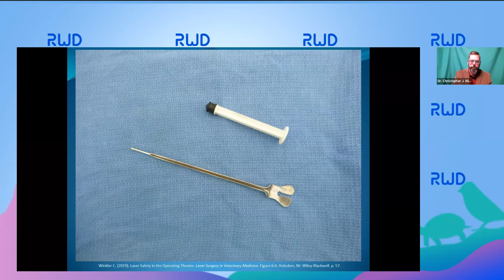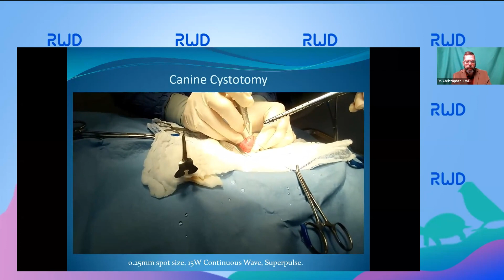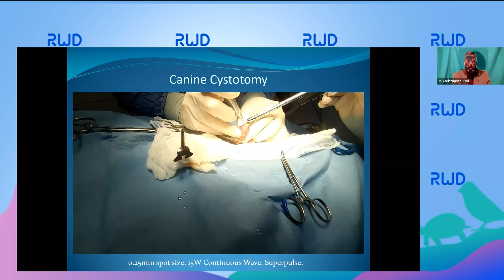Cystotomy is a very satisfying procedure with a CO2 laser. This laser here is set for a 0.25 millimeter spot size at 15 watts continuous wave superpulse. It offers great hemostatic control. Postoperative hematuria and discomfort have been non-existent in the cases we've seen. Just have a feel for how you're going to approach aseptic control with the laser's handpiece. If the stone is large enough, use the stone itself as a backstop as you open the lumen.